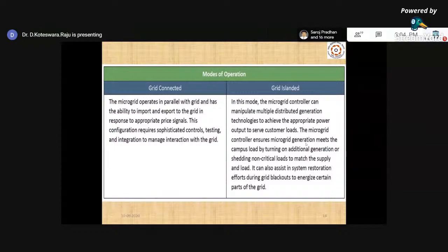Now, grid island mode: here there is no connection to the utility grid. In this mode, the microgrid controller can manipulate multiple distributed generation technologies to achieve the appropriate power output to serve customer loads. Its main aim in island mode is to serve the loads, with decisions taken by the microgrid itself, and it can also assist in system restoration efforts during grid blackouts to energize certain parts of the grid.